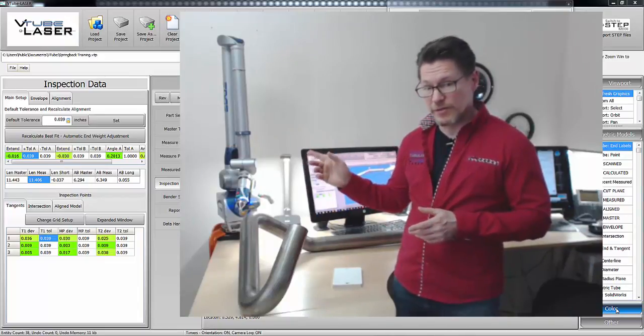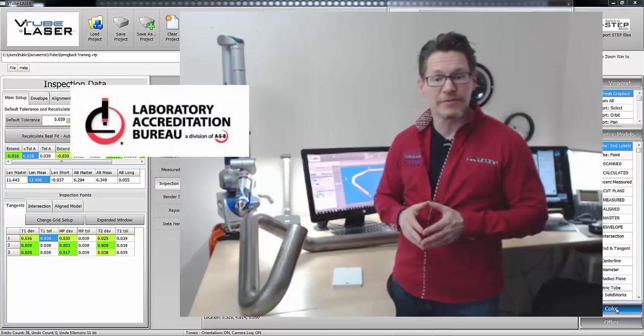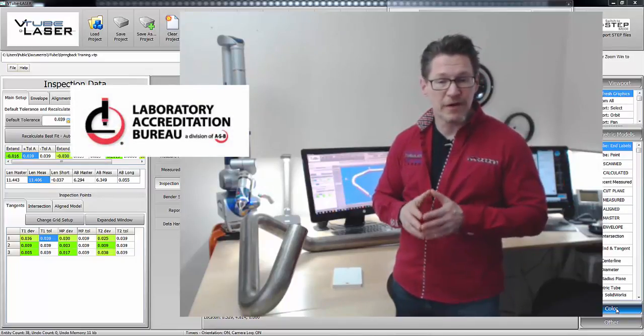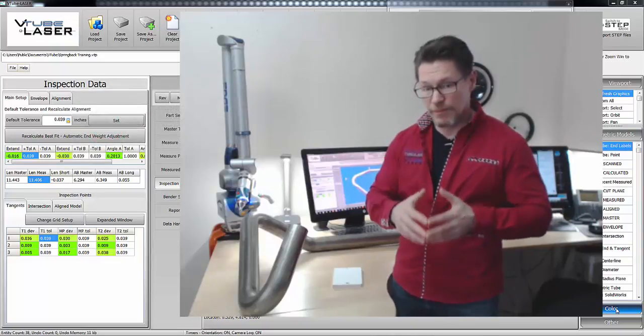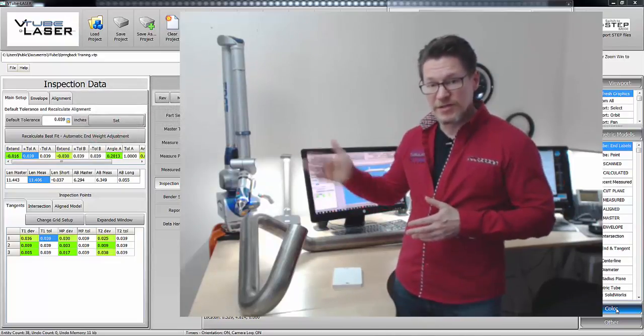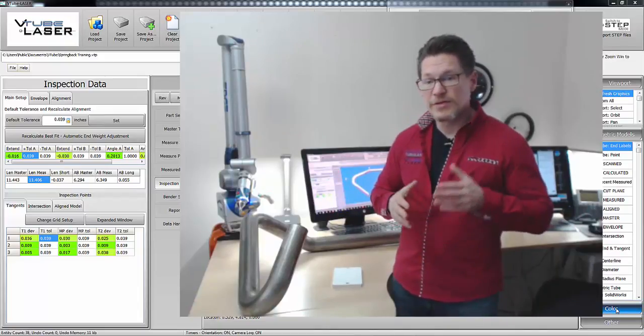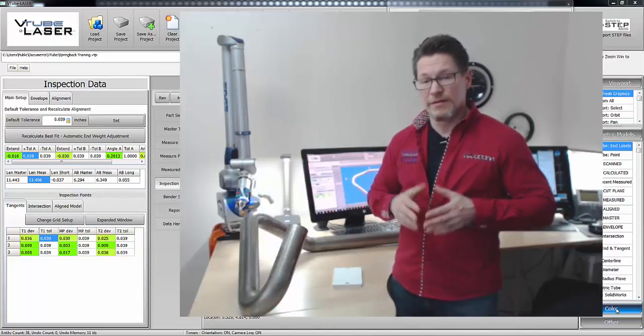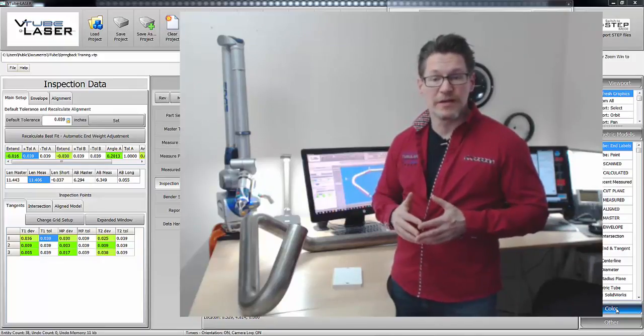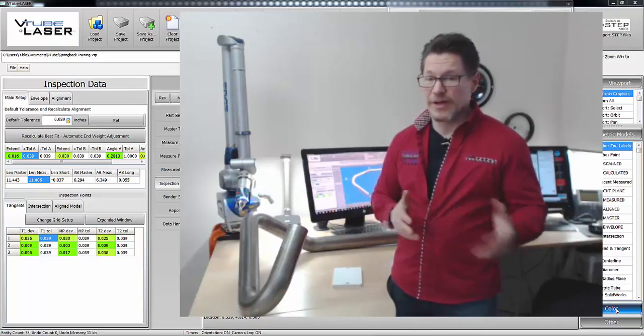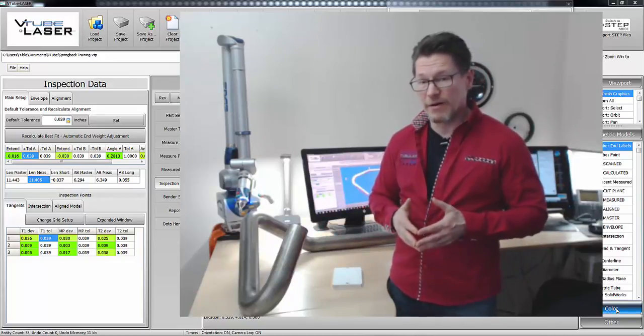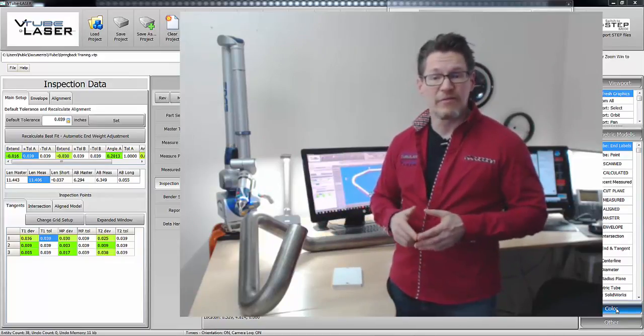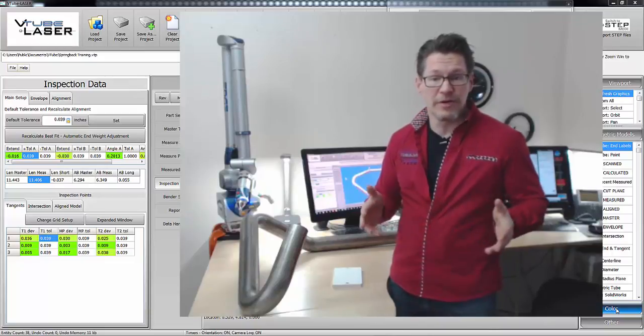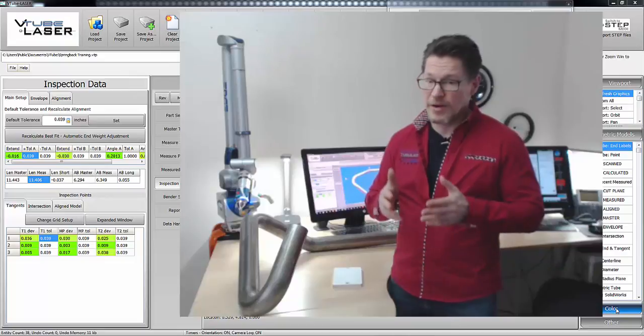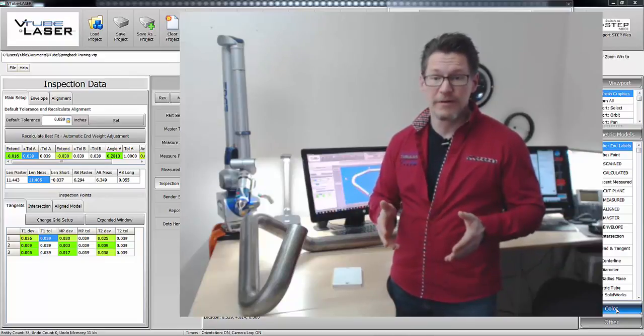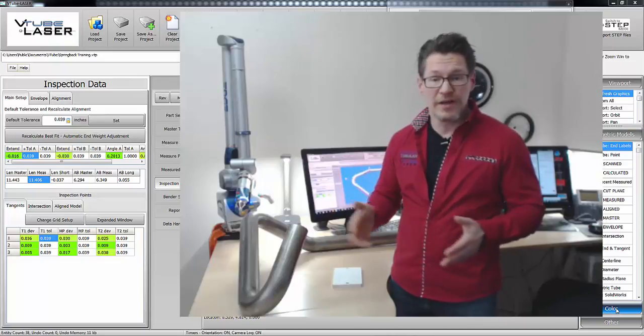The FARO arm itself is always calibrated by FARO in their certified labs, usually once a year. However, FARO expects customers to then calibrate the probes and the laser scanners inside the customer facility. The reason is that the FARO arm is so accurate that it considers no two probes or scanners to be identical. In fact, if you try to measure without calibrating the probes and scanners on a calibrated FARO arm, then the FARO arm will not have enough information about the attached probes or scanners in order to measure the part accurately. So, calibrating probes and scanners is very important. Without it, the FARO arm cannot measure accurately.